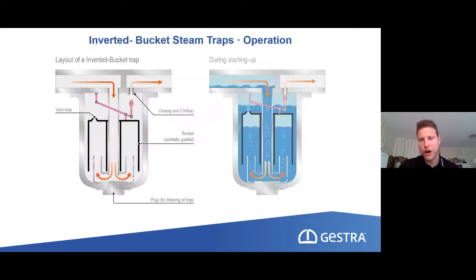So this is a very common kind of steam trap we find very often, for instance, in the United States. The design is similar to the very first steam trap that was invented in the 19th century. It's a so-called inverted bucket steam trap. It works rather simply. We have the entering condensate, which will lift up this bucket here. Or rather, it will not lift up this bucket, only steam can do it.